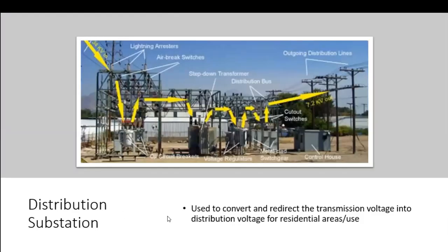A distribution substation, so we're coming off the transmission into the substation. It's used to convert and redirect the transmission voltage into distribution voltage for residential area use. So we've transmitted from a long way away here on the left-hand side in transmission. We come into the substation, we have a substation transformer, and we're going to step down the voltage, and we're going to go out to these distribution voltages right here. You see 7.2 kV, 7,200 volts. Because they have to go shorter distances, for one, and two, they're easier to convert for the voltage that's going to be going into your house.